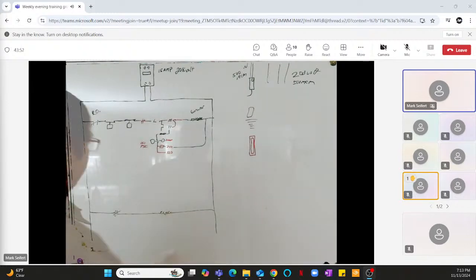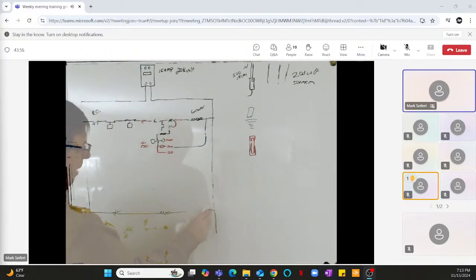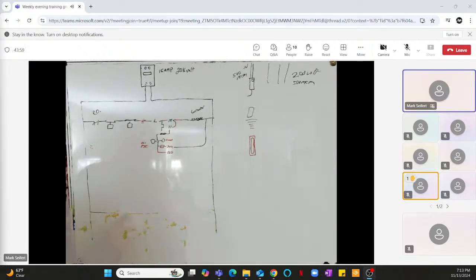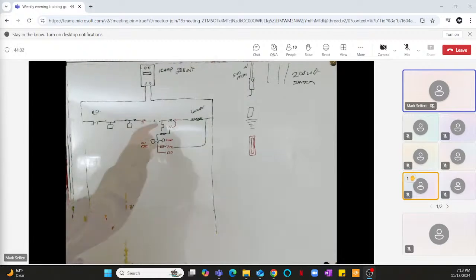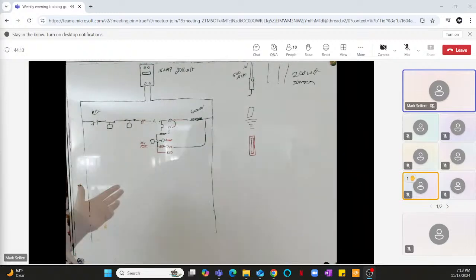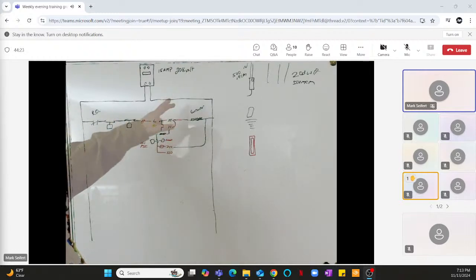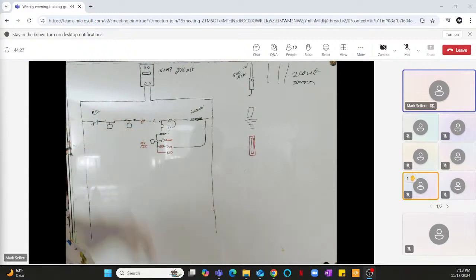I'll double check and I'll look at the wiring diagram. There's like 4 different ways to wire demand cooling. 4-wire, 3-wire. It depends if this is a 3-wire, if this is a 4-wire. There's all these different scenarios. If the demand cooling is wired as a 4-wire, you could put it over here, no problem. Because if it trips on oil, you're going to open up the current sensing relay, and it's not going to power up the solenoid. So I'll get into that when I can look at all the drawings in front of me, because I don't want to mix up some wiring here and then confuse you.